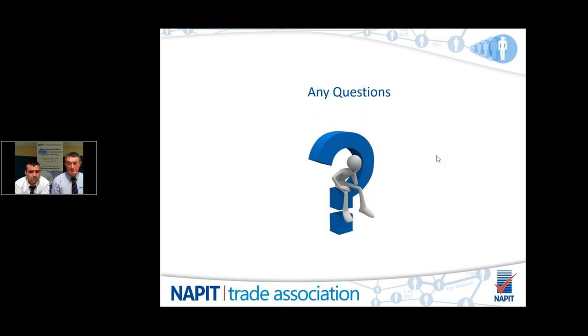And Jeff is saying that most of the EICRs that he carries out are on buildings in use where insulation tests are not possible due to live circuits, and they've just put NA in the megohm charts. Is this the correct way to do this? Use your limitations. Every periodic inspection that you carry out, you fill out your EICR, and there's a place for documented evidence of limitations. Extent is what you do, how much you've tested, so the extent of the installation goes in there. The limitations may very well be that you can't get to any circuits, people don't want you to switch off circuits. It could be the fact that you're working in a very large property and you can't do a Ze. To do a Ze, you've obviously got to make the installation dead to remove the earthing conductor, and therefore that might not be carried out.